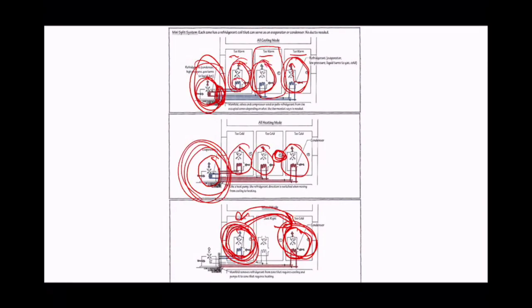But with a VRF system, it's the same type of thing as a mini split or a multi-split system - a multi-split is just a bigger version of a mini split. But it can throttle the amount of cooling from maybe 5% up to 100%. So if your room is just a little too hot, it'll give you just a little bit of cooling by sending just a little bit of refrigerant down there.